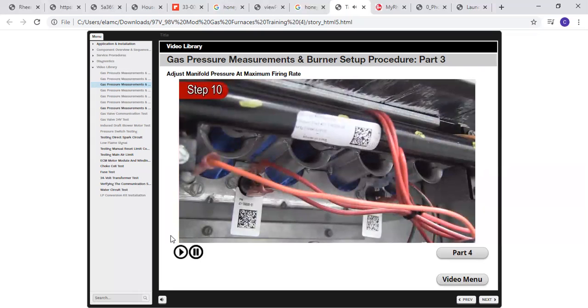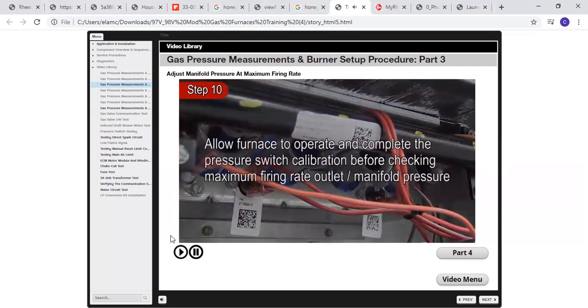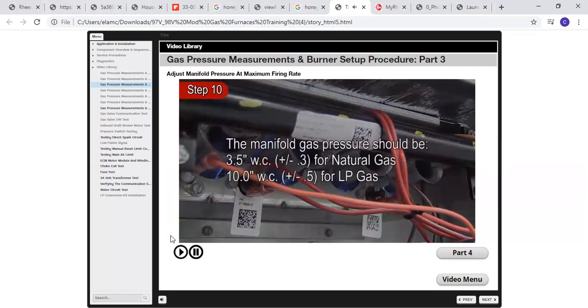Step 10. After ignition, allow the furnace to operate through complete pressure switch calibration before checking the maximum firing rate outlet manifold pressure. Note, the manifold gas pressure is 3.5 inches water column plus or minus 0.3 for natural gas, or 10.0 inches water column plus or minus 0.5 for LP gas.